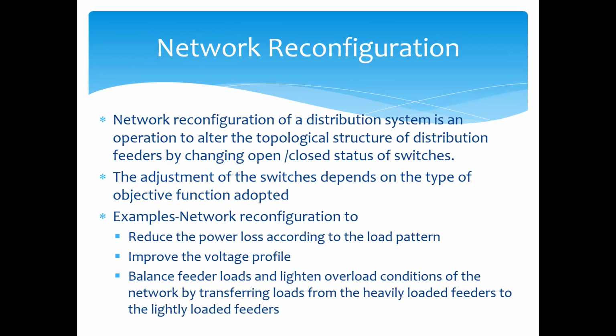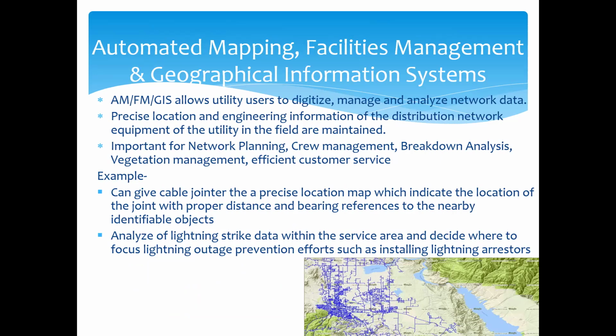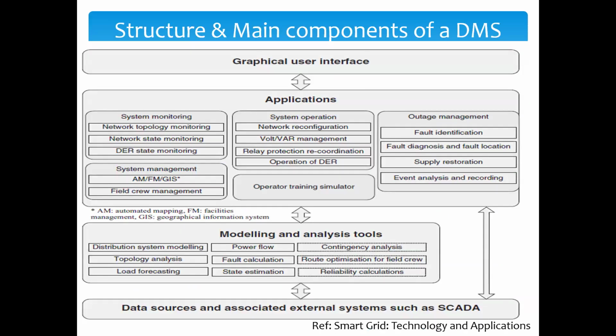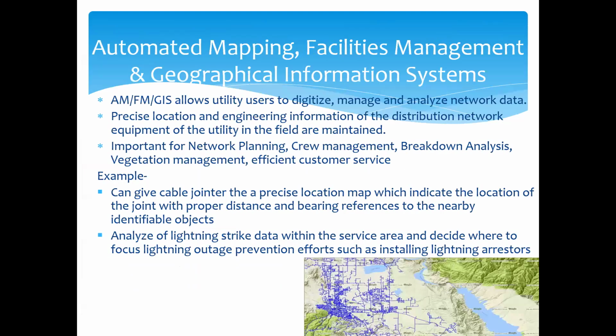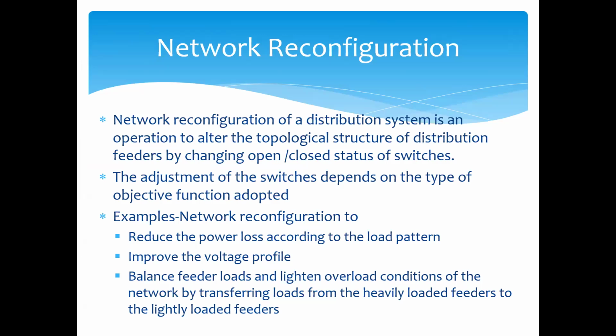Now, you may be able to remember we use a term called network reconfiguration. Here, among the system operation applications, there is a word called network reconfiguration. This is a method of system operation. During system operation, we use that network reconfiguration method. What does it mean? We'll discuss more about that. Network reconfiguration of a distribution system is an operation to alter the topological structure of the distribution feeders by changing the open and closed status of switches.